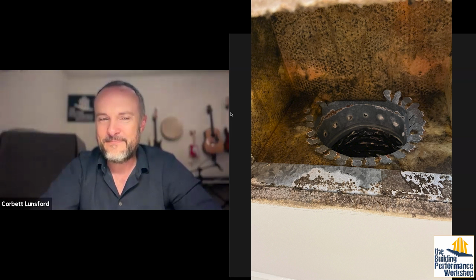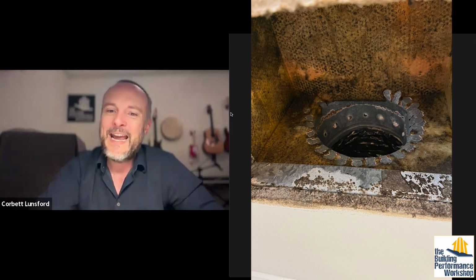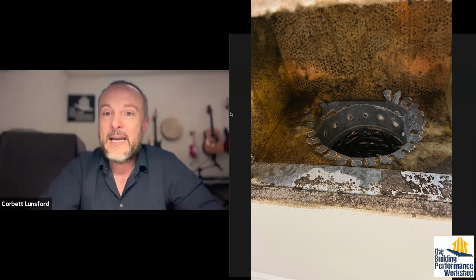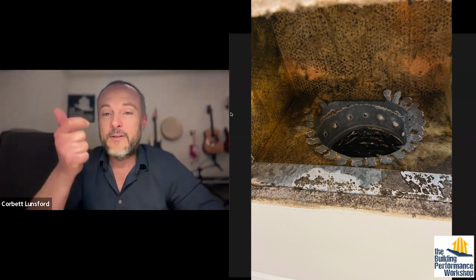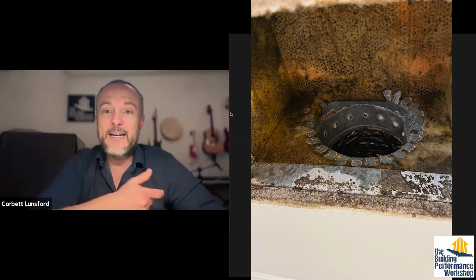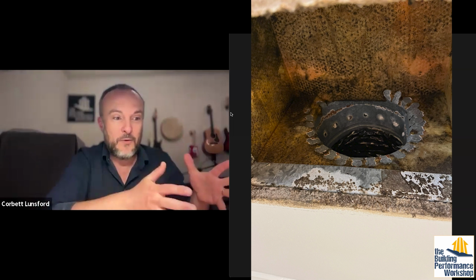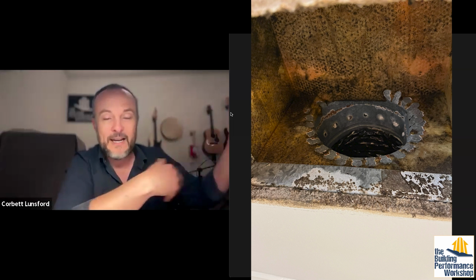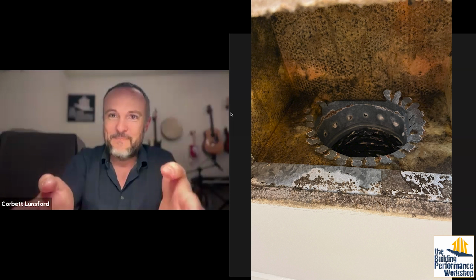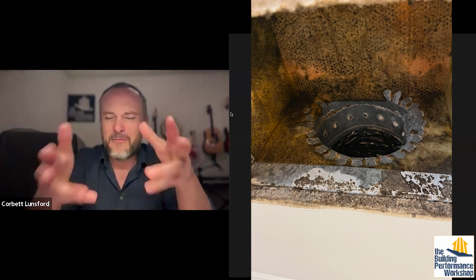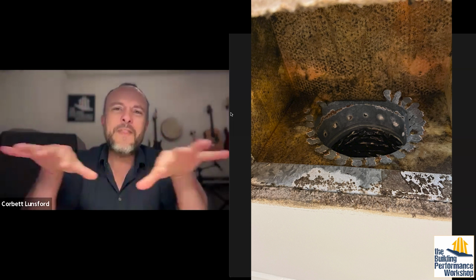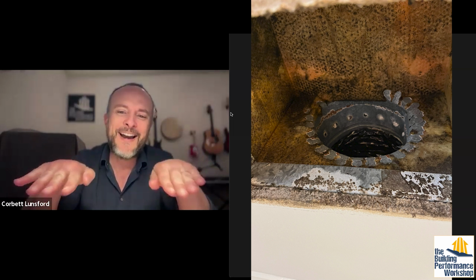But when we have things like this, this is between floors. And this is a duct boot that is coated with mold. One of the reasons it's coated with mold is that it's coated with dust. And that's because partly we've got a leaky duct system that's in an attic. It's picking up dust from the attic and then distributing it into the house. And this duct liner is part of the problem. So there are so many things within this one picture that I want to unpack with you.